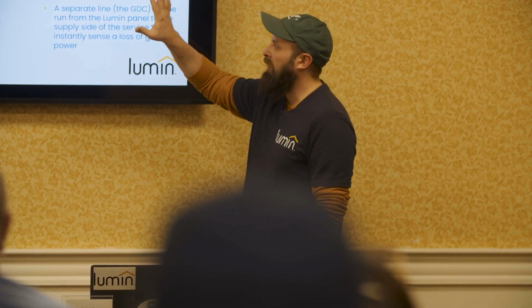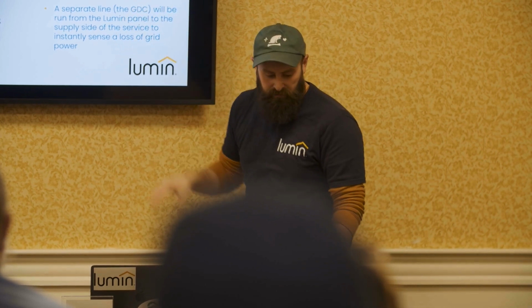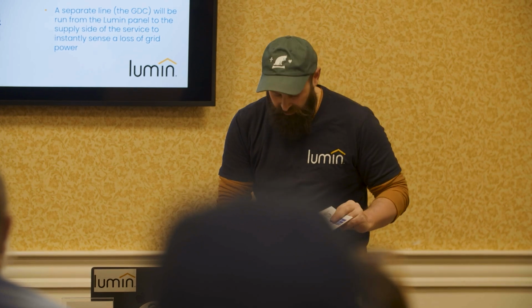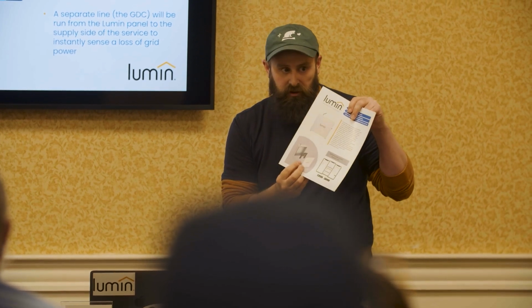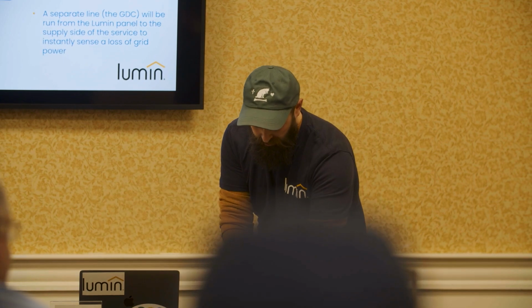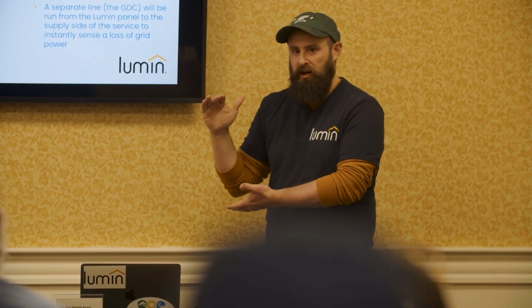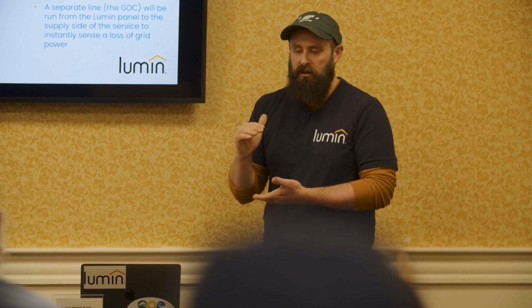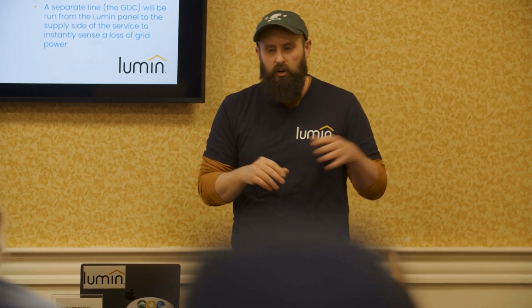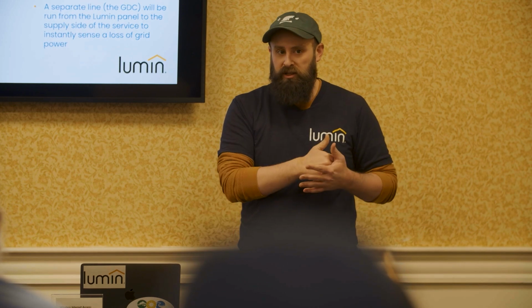There are 2 sensor boards inside the Lumin panel. There's an exploded view on the data sheet you can take later. One sensor board is 60 amp rated, the other is 30 amp rated, and each has 6 relays. So you have 6 relays or lines of control rated up to 60 amp, and 6 rated up to 30 amp. Typically you're using your 60 amp for your 240 loads, your 30 amp for your 120 loads.